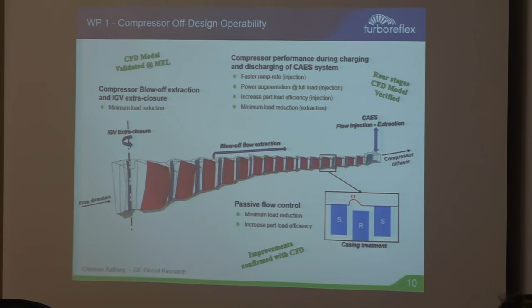Complementary to that is the combustor. Downstream you have the combustion part of the gas turbine, and the hot high pressure turbine. If you want to further reduce your minimum load, you can run into instabilities in the combustor, reaching lean blow-off limits. So this is being tackled here. We try to extend the ranges. Test rigs have been built, data has been acquired, and there's also focus on emission compliance.